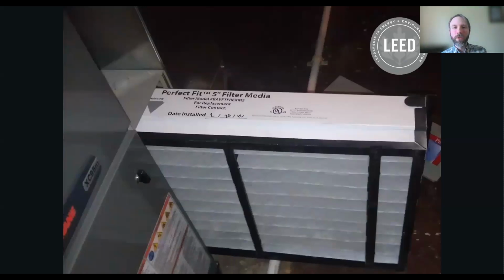Now, when it comes to air filtration, this is important in the homes to protect the HVAC systems and the health of the tenants. Outdoor air quality worsens from pollution and wildfires, and indoor air pollution comes from cooking and other uses of things that off-gas, as well as viral transmissions, the flu, COVID, you name it. The filters catch all of this stuff. LEED is the most sustainable here, requiring at least MERV 8 filters and rewarding for MERV 10. Enterprise requires MERV 6 via Energy Star on new construction, and NGBS rewards points up through MERV 14, but has no requirements.